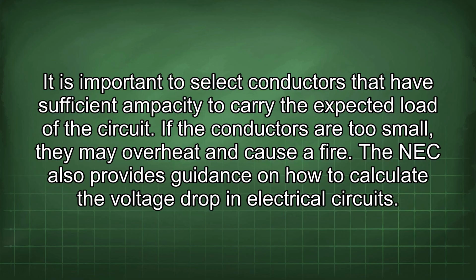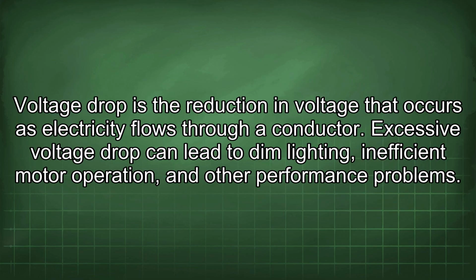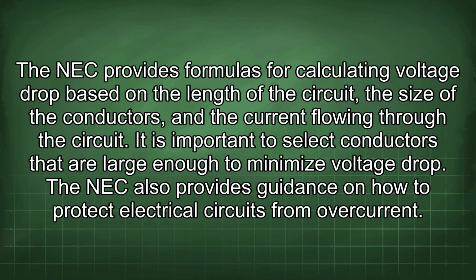The NEC also provides guidance on how to calculate the voltage drop in electrical circuits. Voltage drop is the reduction in voltage that occurs as electricity flows through a conductor. Excessive voltage drop can lead to dim lighting, inefficient motor operation, and other performance problems. The NEC provides formulas for calculating voltage drop based on the length of the circuit, the size of the conductors, and the current flowing through the circuit. It is important to select conductors that are large enough to minimize voltage drop.